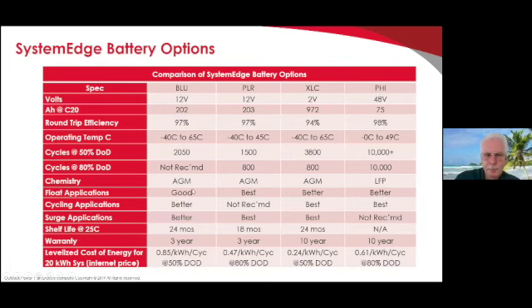So just some relative ratings on float and cycling applications, and surge applications. The PLR and XLC are really good surge batteries. They are not recommended for the SimpliPhi. So you need to look at our sizing tool, we have a surge chart, and I'd recommend you don't exceed the kWh spec. Compare that surge spec to your kWh spec on the Simplify, because these are not surge batteries.